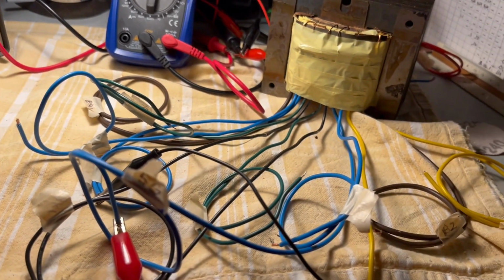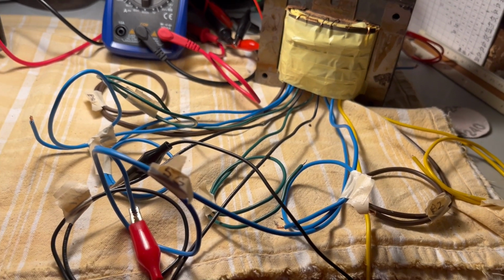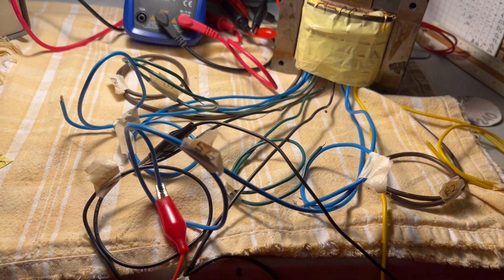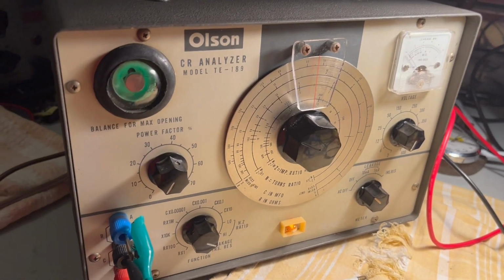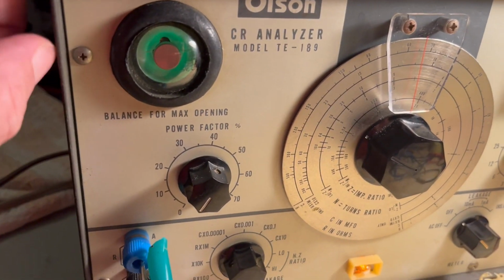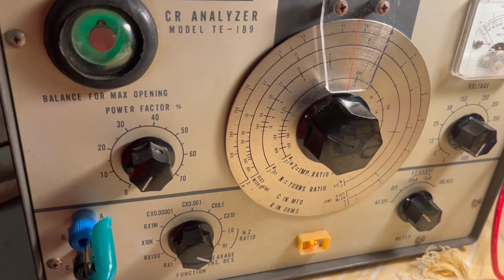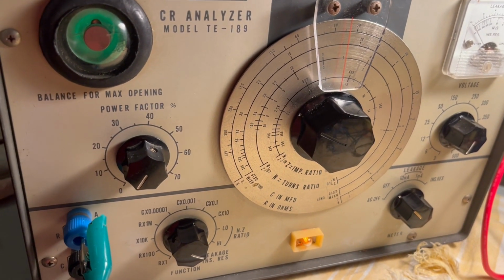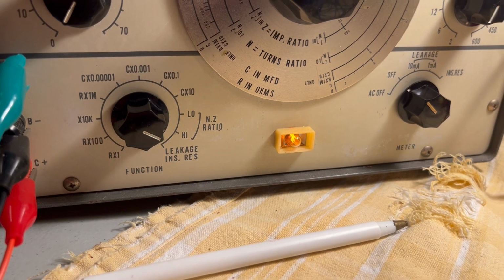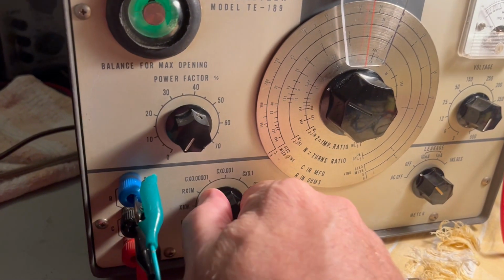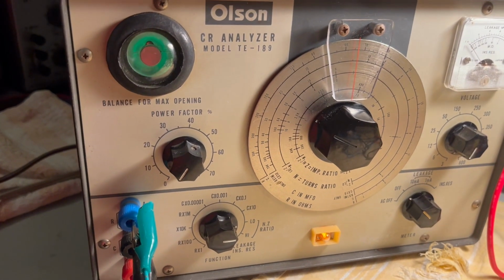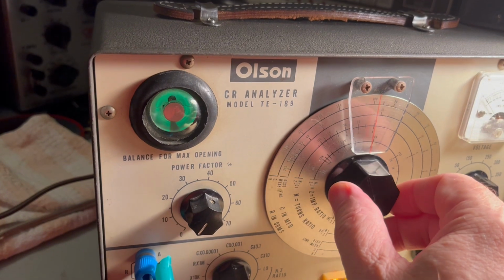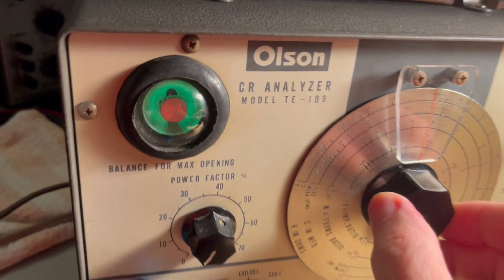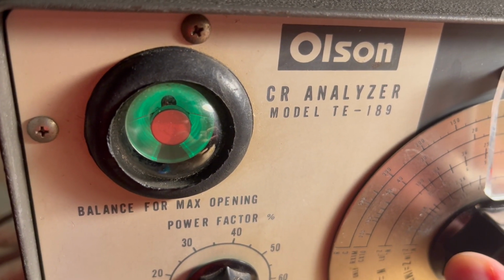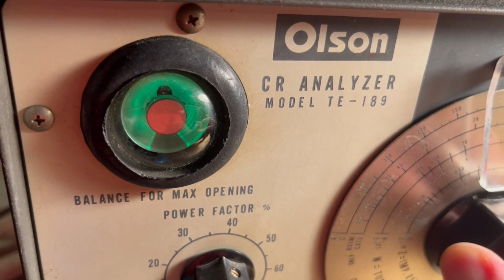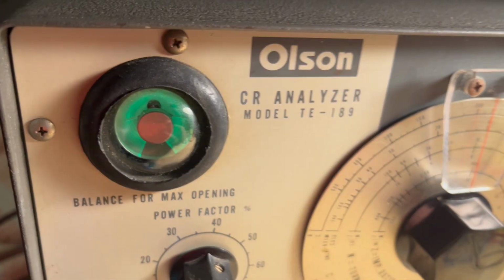And the reason I'm picking this 25/50 volt coil is because it's fairly close to the primary. The primary is 110 or 120, something in that range. Okay, so right now you use this green eye up here in the corner and the balance wheel over here in the center, and right now I've got it set to high, but there's also a low, and I'm going to set it to low for the purposes of this. And you turn the balance wheel and you get an open eye right there. The way that you can tell that it's right is that both the light colored eye and the dark open section overlap. And the closer you can get that, the better off you are.